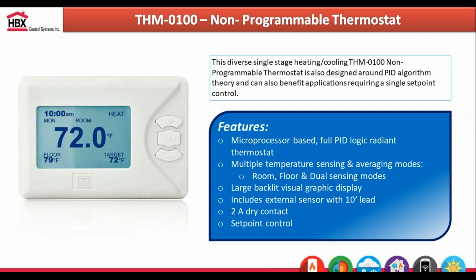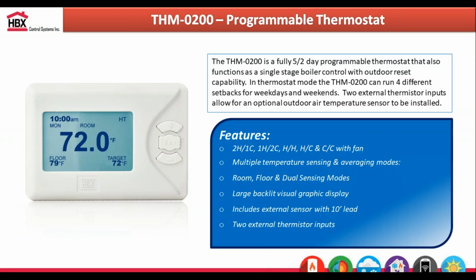So in Western Canada, I would say a good chunk of the jobs, you just would use this stat as a digital aquastat. So you can put it into SETPOINT mode. You can actually use the sensor that comes with the stat and use that as a digital aquastat, just because we're very price competitive to an actual mechanical aquastat, but you get a digital display with it. So it's kind of a no-brainer where you can use it as that SETPOINT controller. We also have a THM 200 option. Again, same option as our THM 100, except we can do heating and cooling at the same time. So we can do up to 3 stages with the THM 200, and it can actually be used as a single stage boiler controller with outdoor reset if you really wanted to.